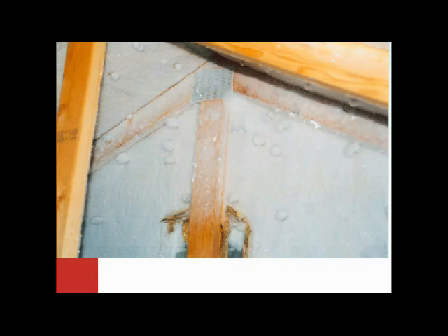This is a classic slide sent to us from the folks in Montana. Paul Cheetah shared this with us from the state of Montana. This is what happens when you have a full-blown disconnect of a supply run up in a vented attic, and this is up in a bitter cold climate. Tremendous condensation and frosting and ice.